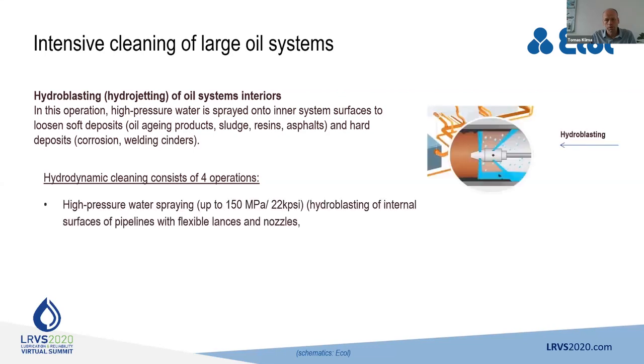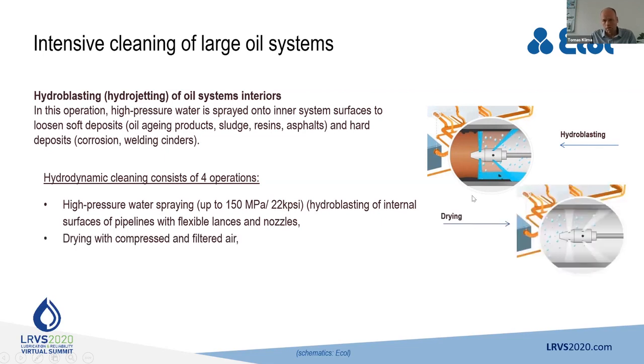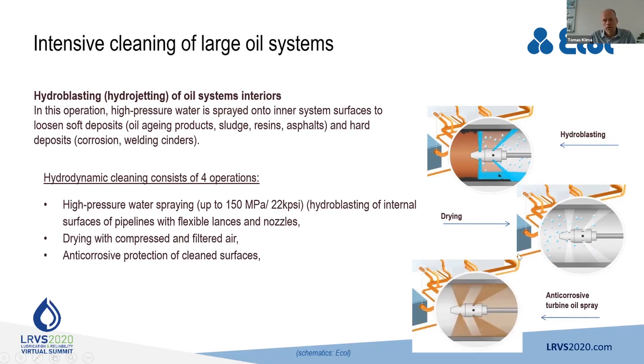The process consists of 4 operations. You see on the pictures, the first operation is hydroblasting, where the high pressure water nozzles are penetrating the deposits, flowing out with the water, and using usually high pressure up to 150 megapascal. And following that, we dry the pipes using high pressure filtered air, to remove the remaining water droplets, and just after that spraying the internal surfaces with turbine oil or with the oil that is used for operation, for example, compressor oil or hydraulic oil if we are doing the cleaning on a hydraulic system. So with the operation oil.